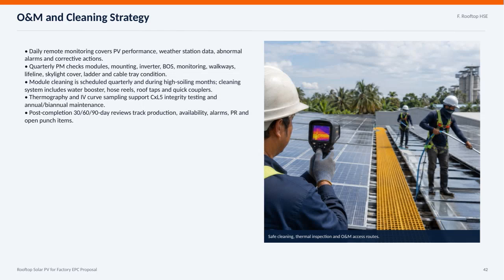On this slide, we're focusing on the O&M and cleaning strategy for the rooftop solar PV system as part of our factory EPC proposal. The key aspect here is maintaining safe cleaning, thermal inspection, and access routes to ensure ongoing system reliability. Daily operations include remote monitoring that tracks PV performance, weather conditions, and any abnormal alarms, allowing us to take corrective actions promptly. Then, on a quarterly basis, we perform preventive maintenance checks covering all critical components such as modules, mounting systems, inverters, and balance of system equipment, as well as walkways, lifelines, skylight covers, ladders, and cable trays.